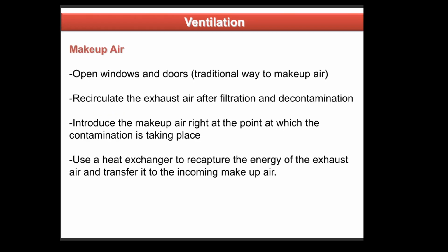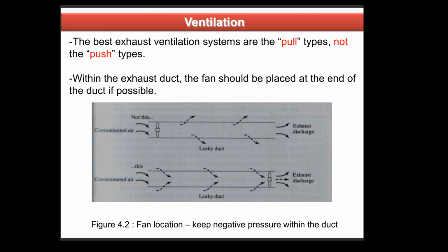Makeup air. Open windows and doors is the traditional way to make up air. Recirculate the exhaust air after filtration and decontamination. Introduce the makeup air right at the point at which the contamination is taking place. Use a heat exchanger to recapture the energy of the exhaust air and transfer it to the incoming makeup air. The best exhaust ventilation systems are the pull types, not the push types.